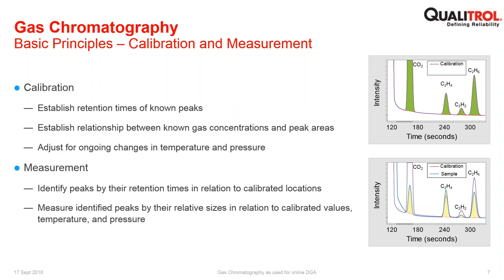For measurement, you identify the peaks from the retention times in relation to calibration locations. So if you have the same gases in the measurement system as you had in the calibration system, which for dissolved gas analysis, we know what those gases are, then we will see those gases being eluted at the same time. And if we look at the relative size and relate it back to the original calibration, we can get an accurate measurement of the quantity of the dissolved gases present.